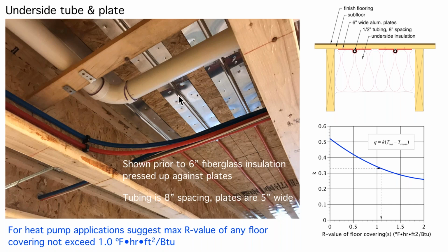So again, you can see the plates are stapled up nice and tight. I prefer to work with aluminum PEX tubing whenever we're working with aluminum plates, and that's not a code requirement. The reason I like aluminum PEX is that the coefficient of expansion of the tube and the plate are almost the same. So you get very little differential movement between the tube and the plate as it heats and cools, and that minimizes any potential for little ticking sounds, expansion and contraction sounds, okay?